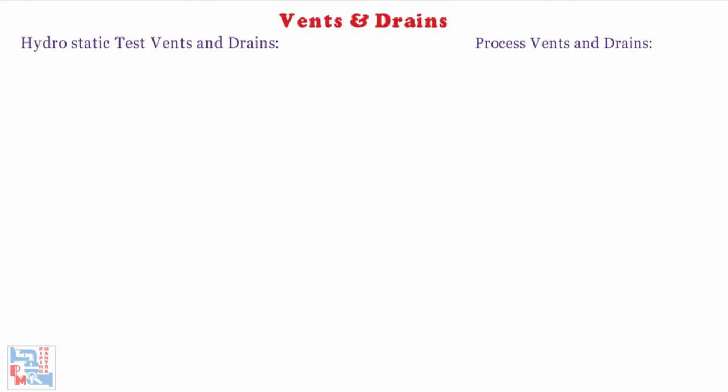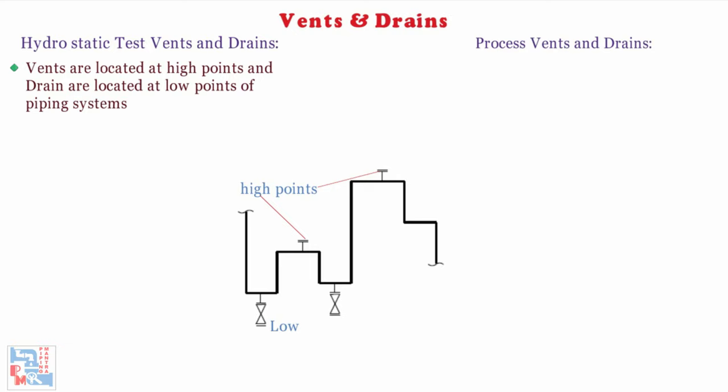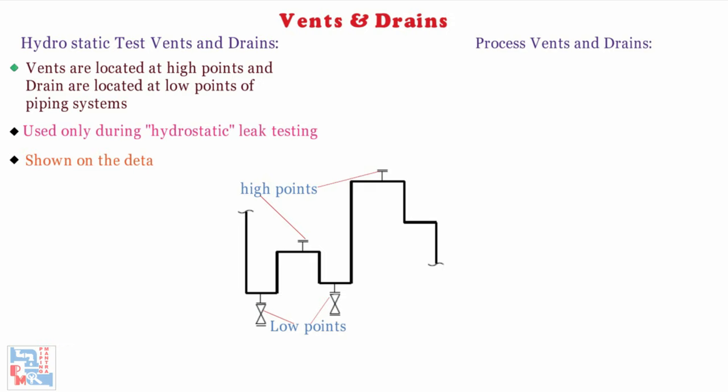Hydrostatic test vent connections are located at high points and drain connections are located at low points of the piping system based upon the physical piping configuration. These connections are used only during hydrostatic leak testing of the piping system. Hydrostatic test vents and drain connections are shown on the detailed construction piping drawings.